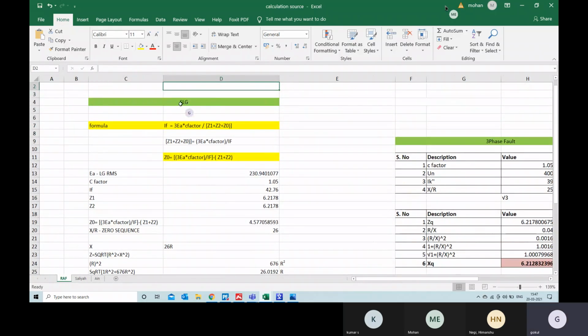So here comes the single line to ground fault, SLG. The formula is basic, like we would have studied in college: to find the single line to ground fault, it's 3 divided by C factor into Z1, Z2, and Z0 - the sequence impedances. Z1 is the positive sequence, Z2 is the negative sequence, and Z0 is the zero sequence. Remember that.